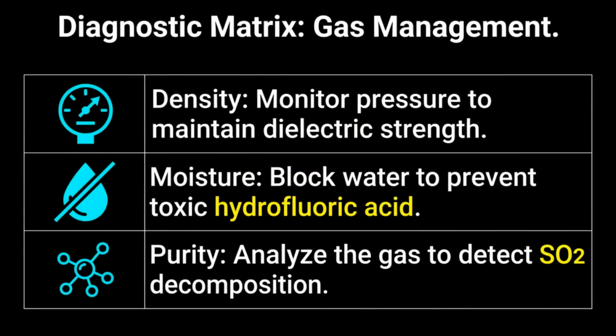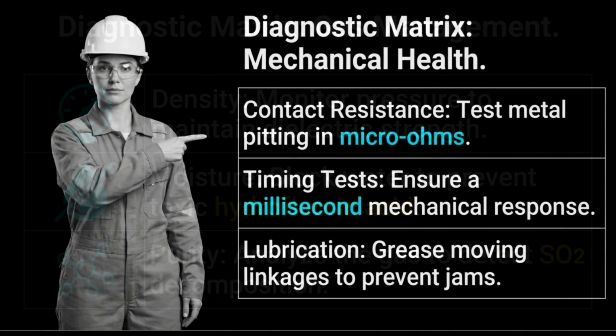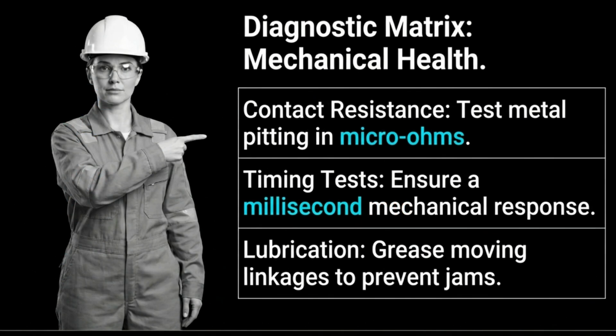Gas management diagnostics include monitoring density to maintain dielectric strength, blocking moisture to prevent toxic hydrofluoric acid, and analyzing purity to detect sulfur dioxide decomposition. For mechanical health, test contact resistance in microohms to check for metal pitting. Perform timing tests to ensure a millisecond mechanical response, and grease moving linkages to prevent jams.